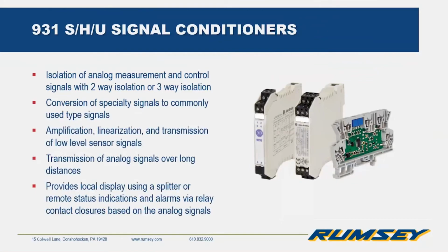Moving on, we'll get into signal conditioning. So essentially, signal conditioners are taking in, most of the time, an analog signal or some other type of signal, and then converting it to another easier to transport signal. So you can use these to take a 4 to 20 signal in and clean that up and send it out to a PLC, or you can reduce the cable runs of something like a thermocouple wire, and really provide cost savings.